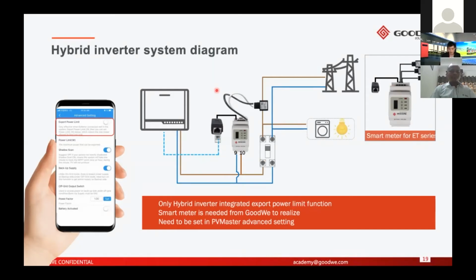After the connection, you just need to open your app, the PV Master. In the PV Master app, you can click the export power limit. Just enable this function, and here you can set the power limit value, how much power you want to export to the grid. So for the hybrid, for the storage inverter, it's very simple. You just need to do it in the PV Master app.